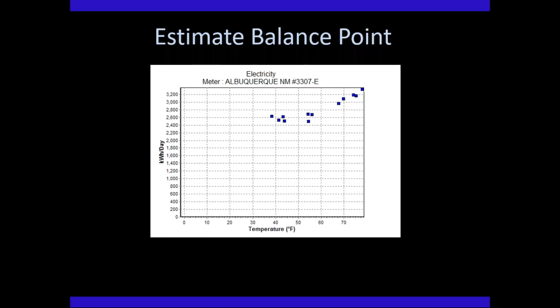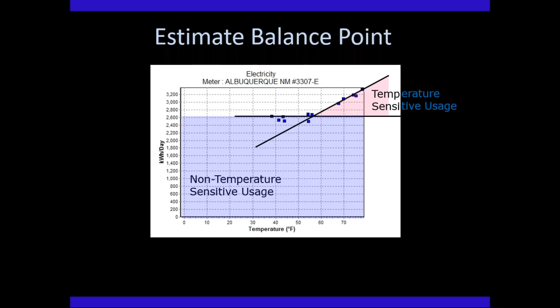When we do this metrics tuning, one thing we do is estimate the balance point using this same outdoor temperature graph. We imagine a horizontal line through a portion of the bills, and another line slanting up to the right or left. Where these two lines intersect is what we call the balance point, the temperature at which the building starts to cool. Here, this building starts cooling at about 56 or 56.5 degrees, which is pretty cold.